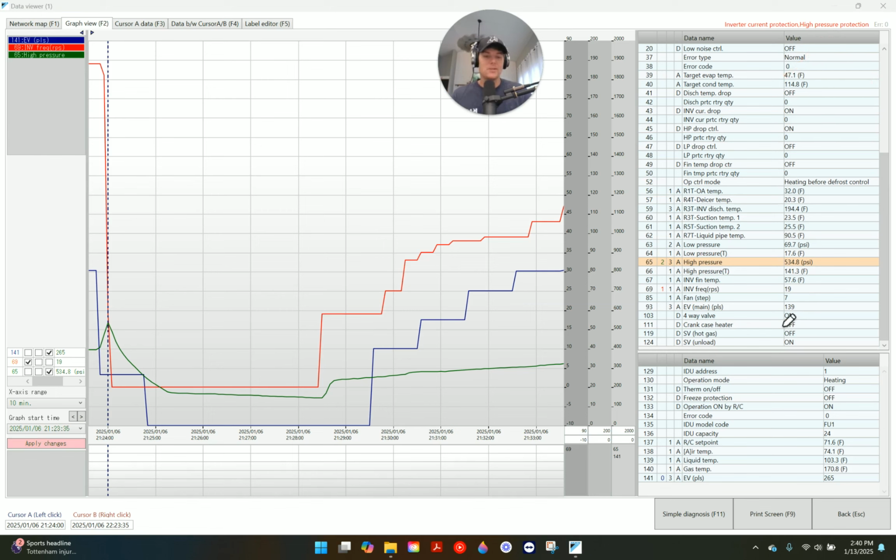Now remember, this all depends on how you set it up. It could be every 30 seconds. It could be recorded every 60 seconds. If you're doing every 10 seconds, that's too fast. It's not going to populate data. So, I mean, this number could have actually been 600 PSIG. The system just didn't catch it in the increments that we're recording that data in. However, it's enough to turn this compressor from way up here to all the way down here at the bottom.